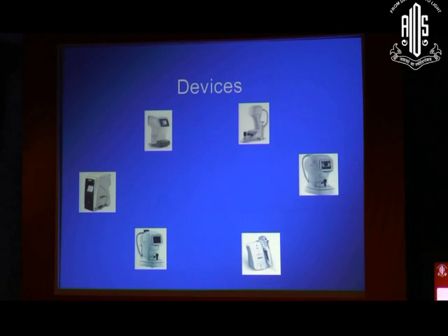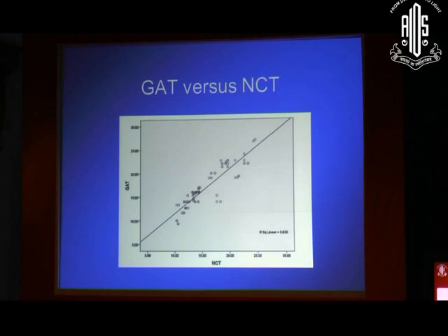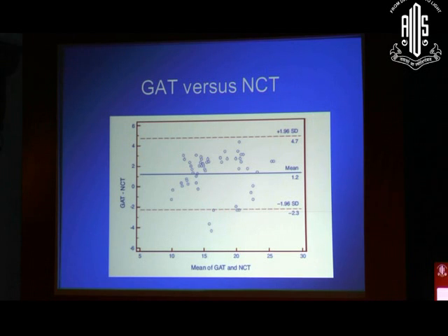There are a huge range of tonometers available. But if you compare Goldmann Applanation Tonometry, the gold standard for tonometry, versus non-contact tonometry, you find that in general, NCT tends to underestimate a little bit compared to Goldmann Applanation Tonometry. And if you look at this graph, which basically tells you how different the two instruments are, you find that 95% of the time your values could range between minus 2 to plus 5.